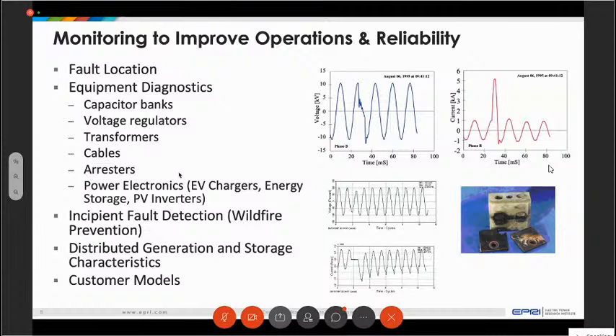In California and Australia, these arcing conditions can result in wildfires. So it's absolutely critical to be able to identify these exactly when they occur and solve the problem. Get rid of that vegetation that's causing the arcing, or that arrestor that's about to fail. And when it does fail, it could cause a fault that could cause a fire. So there's tremendous value in being able to identify from a waveform the potential causes of that disturbance. That's a significant opportunity for artificial intelligence and data analytics to help with equipment diagnostics and fault detection and resilience and reliability improvement.